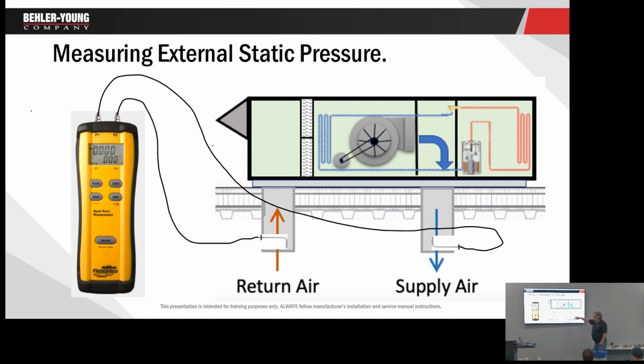So face the tube into the airflow. I got 0.5 inches coming out of the unit. I have 0.4 going into the unit. 0.4 on the return, 0.5 in the supply. Now, where do I do that? Can I stick that probe in the door of the unit?